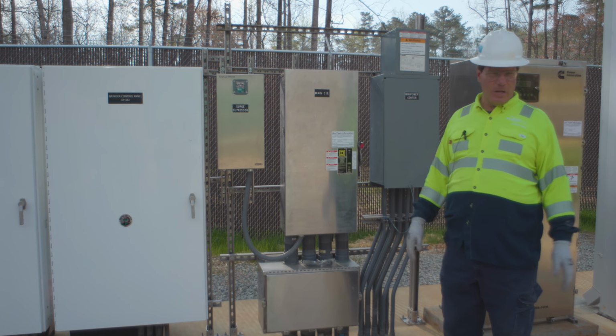And then this is the Mission RTU. The Mission RTU is very simple. It pretty much is just used for power fail and high level. So they don't usually connect anything else. They might connect generator run to it sometime, but for the most part it's just generator, high level, and power fail. We open up the cabinet. Here's all your control breakers that distribute the power throughout the various panels, including the PLC panel. You can turn off the PLC panel from over here.